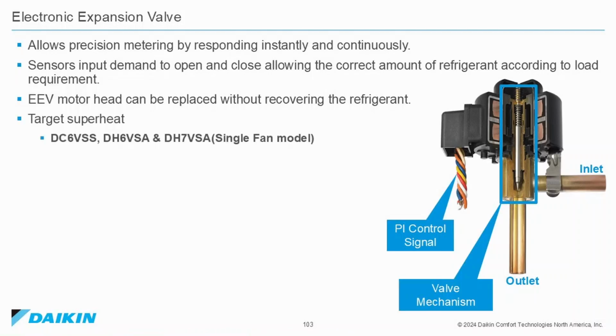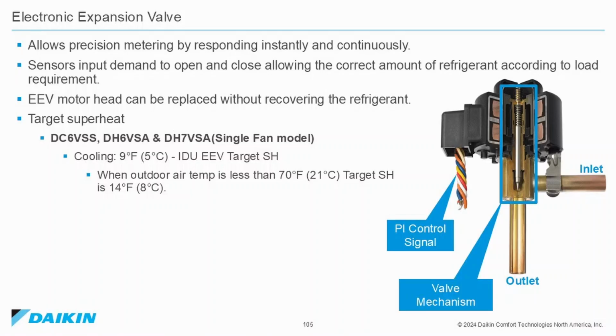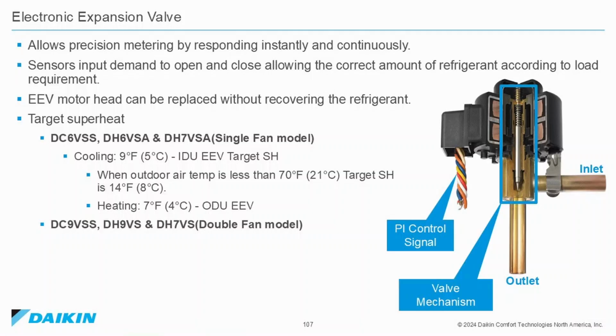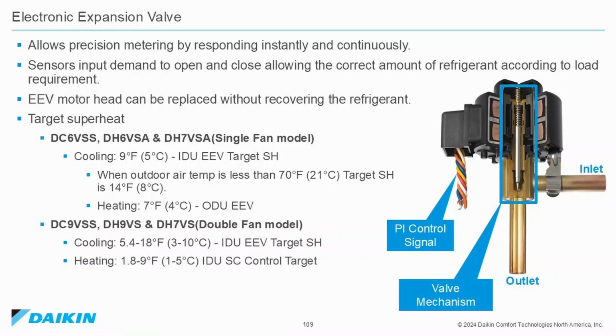Target superheat for the DC6 VSS, DH6 VSA, and the DH7 VSA single fan models. In cooling, has a 9 Fahrenheit indoor unit EEV target superheat. When the outdoor air temperature is less than 70 degrees Fahrenheit, the target superheat is 14 degrees. In heating, there is a 7 degree superheat at the outdoor unit EEV. The DC9 VSS, DH9 VS, and DH7 VS double fan models. Cooling 5.4 to 18 degrees is the indoor unit EEV target superheat. And in heating, it's 1.8 to 9 degrees indoor unit subcooling control target.